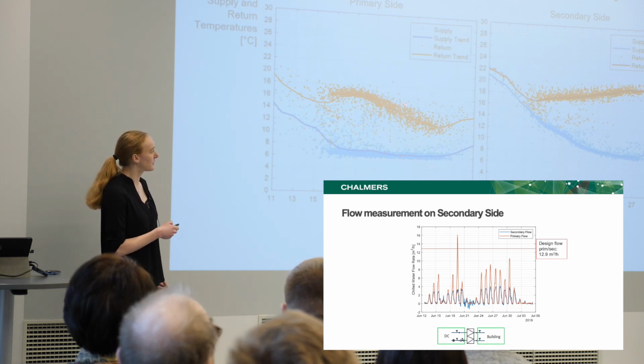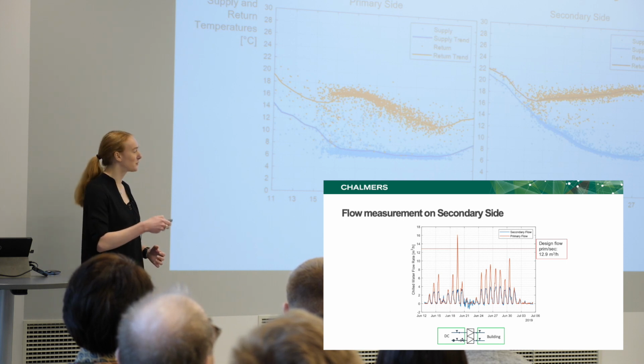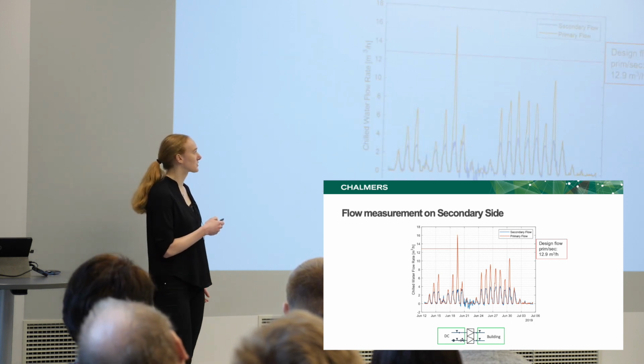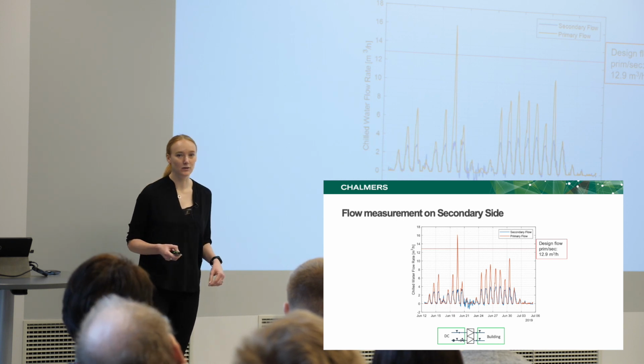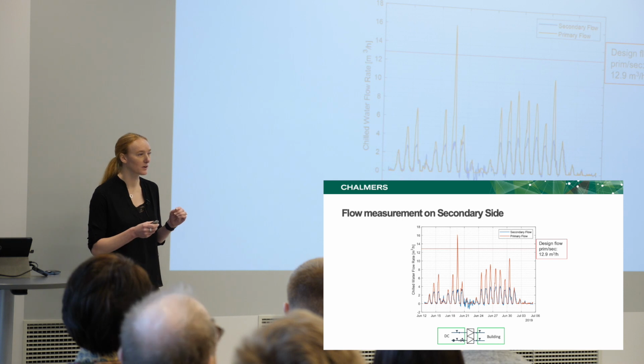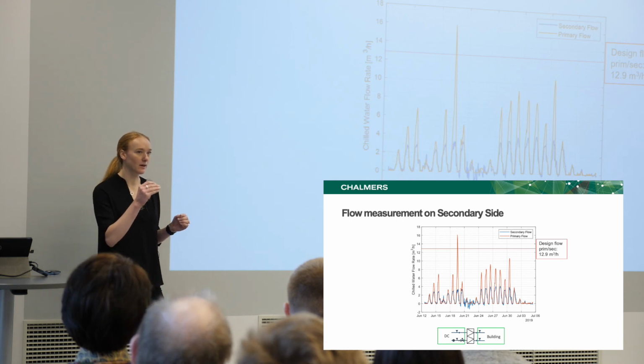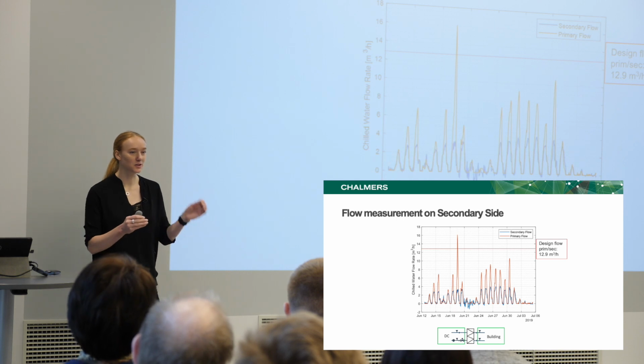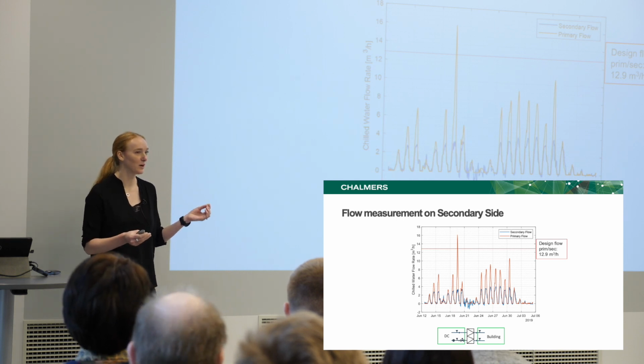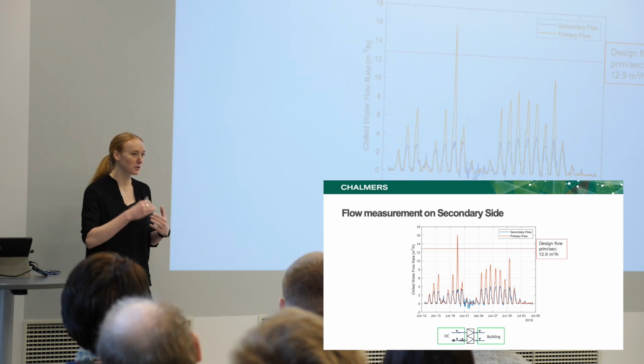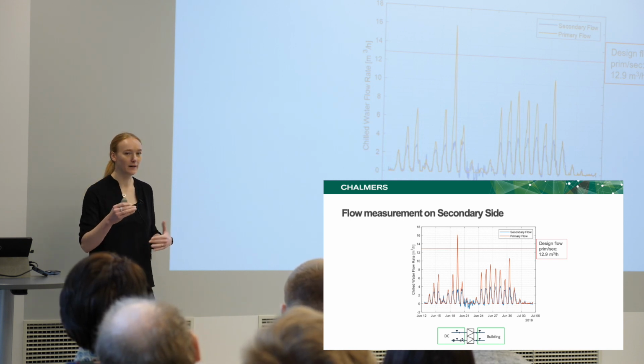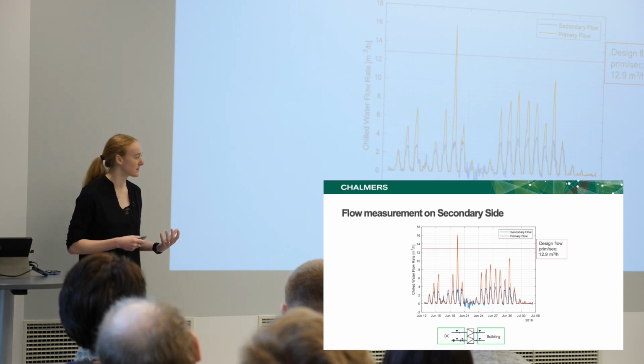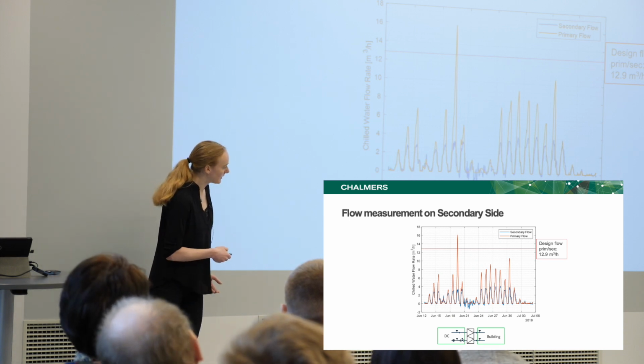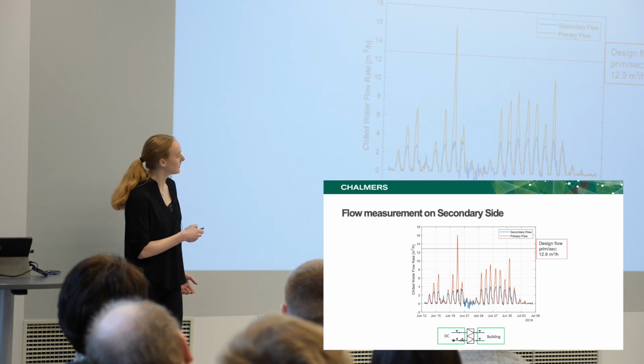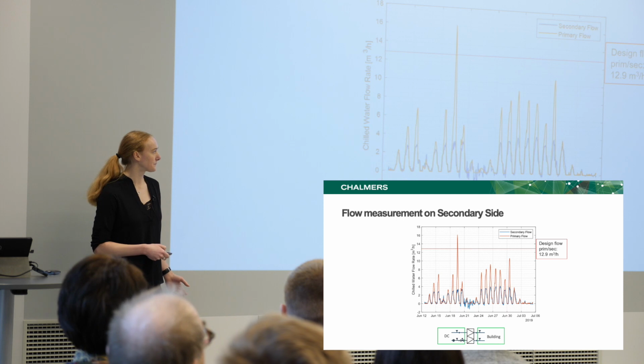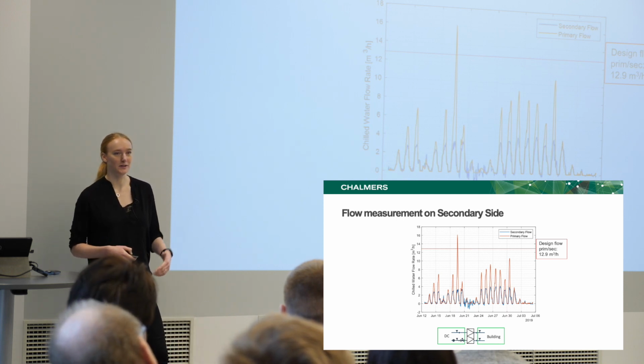These low temperatures here are connected to the higher flow on the primary side, which was caused by the supply temperatures being too close to one another. So the building owner set the supply temperature, let's say, at 7 degrees. And then the district cooling temperature was maybe 6.5, maybe up to 7 sometimes, which caused the control valve to open fully, and the flow through the heat exchanger on the primary side here gets way higher than on this side, consequently causing the return temperature to drop.